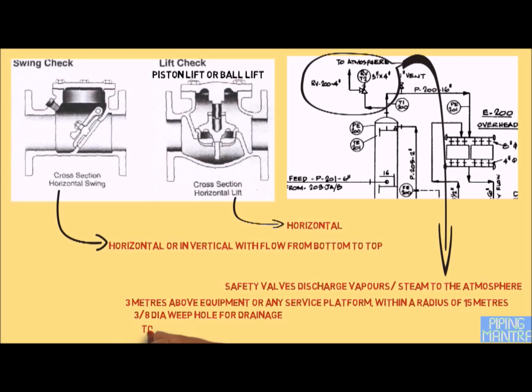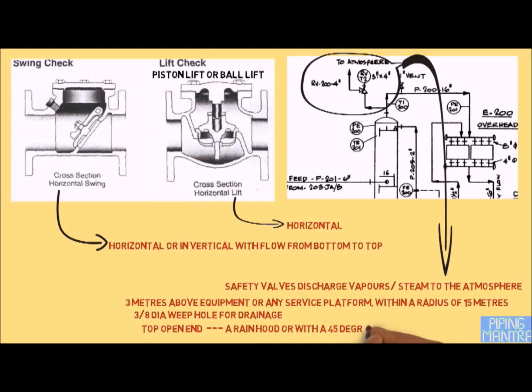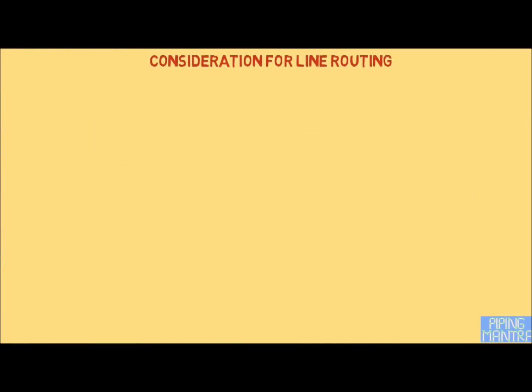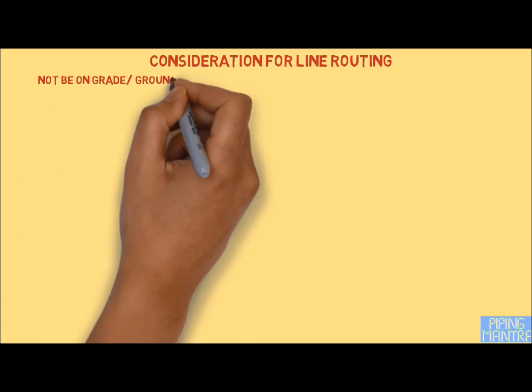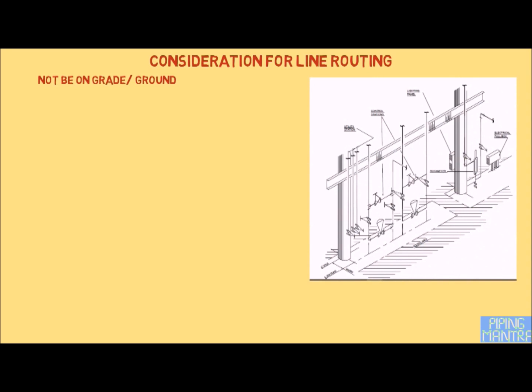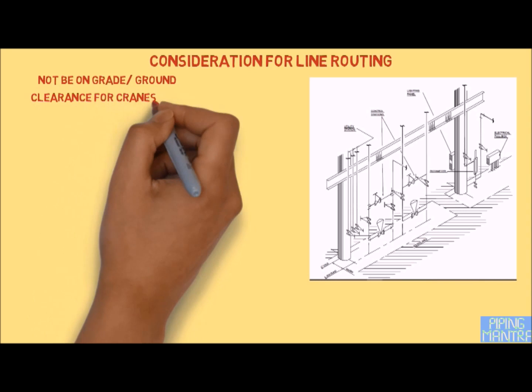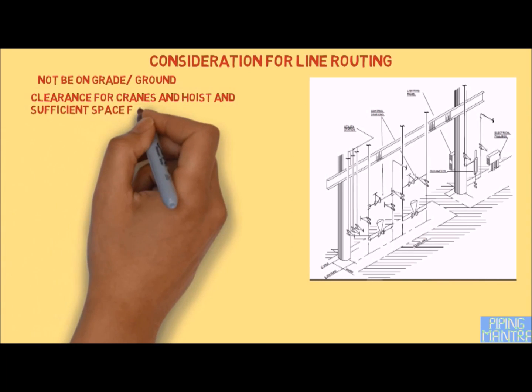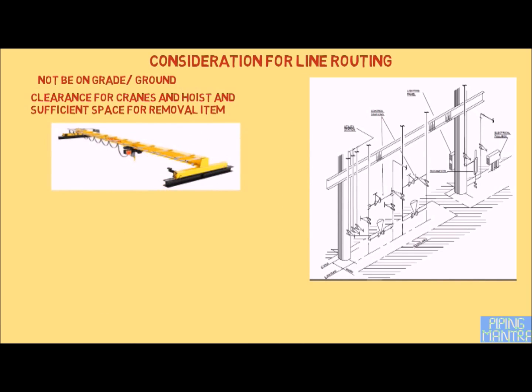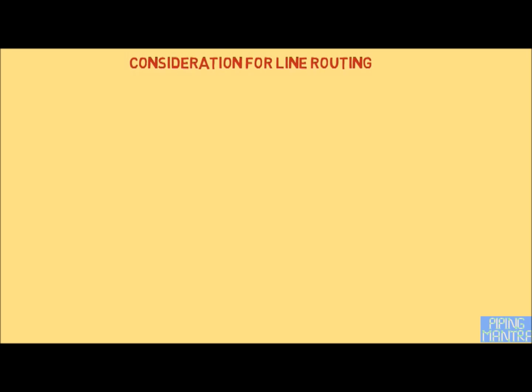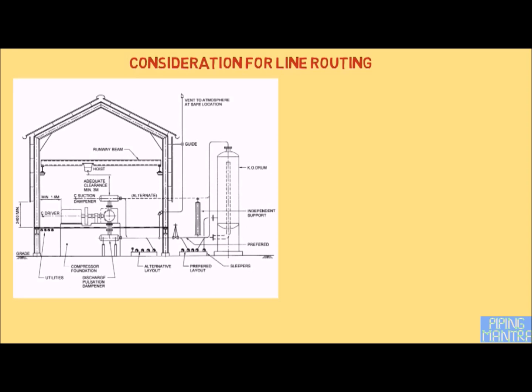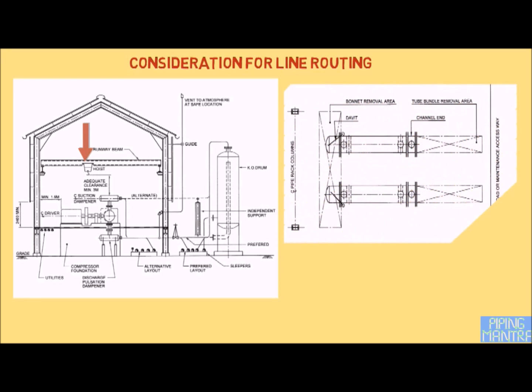For all safety valve discharge lines, the top end should be provided with a rain hood to prevent rainwater accumulation, and a bird screen or a 45-degree elbow cut at the open end should be provided to prevent birds from entering. Piping should not be routed at grade level wherever frequent movement occurs. Piping should have clearance for cranes and hoists, and sufficient space for removal of equipment. Provision of lifting devices such as davit sockets or chain-pulling blocks should be made for valves weighing more than 45 kg.